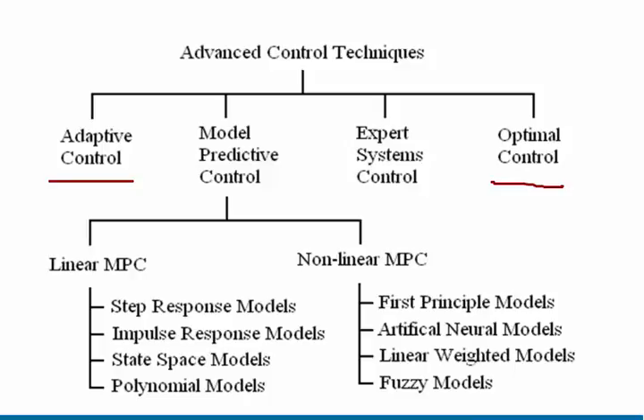When we take it to the next step and wish to introduce more variables, we go to something like a predictive model. The predictive model looks at feedforward mechanisms, which give you the ability to overcome dead time, look at the various relationships, and then split those into two groups: a linear predictive model or a non-linear predictive model.